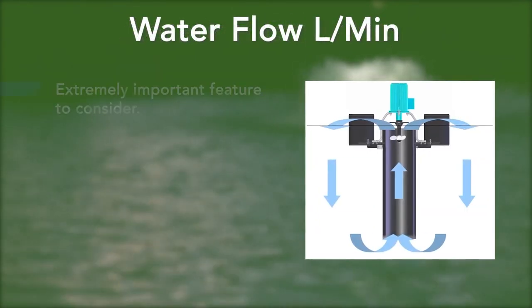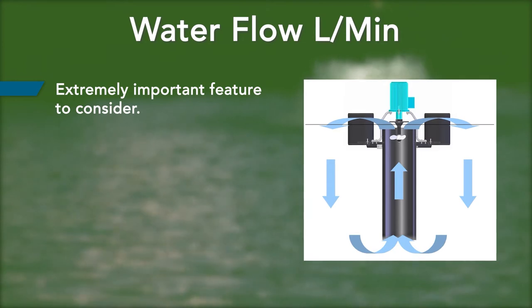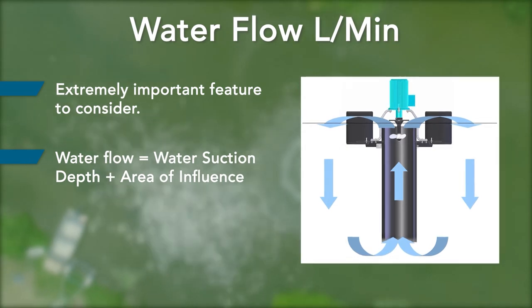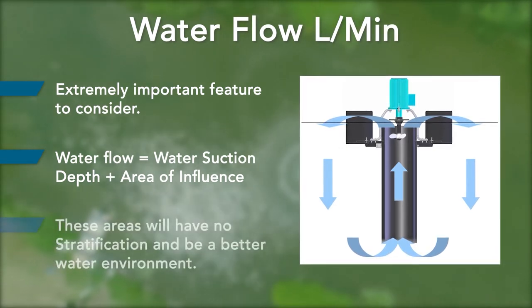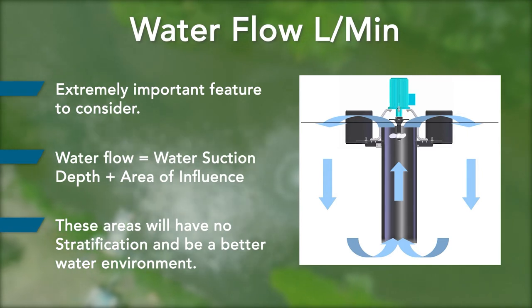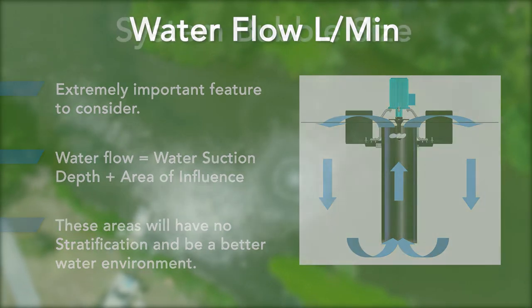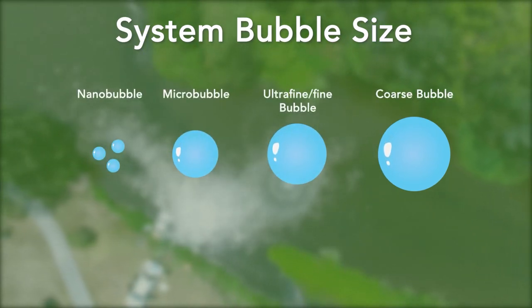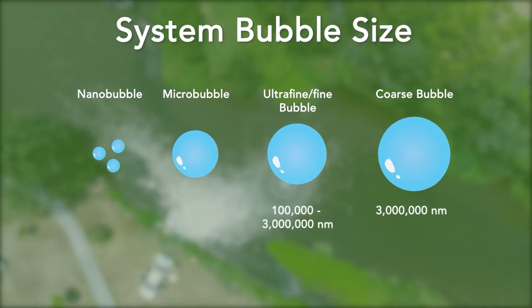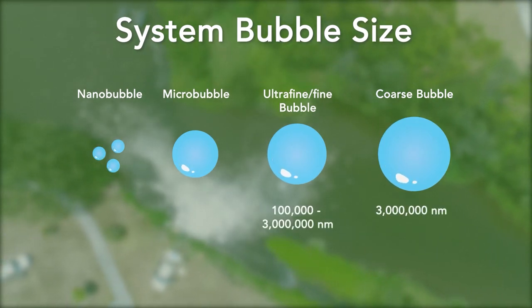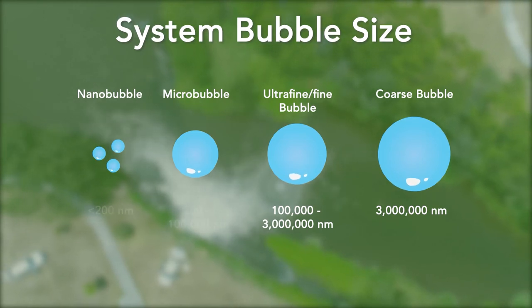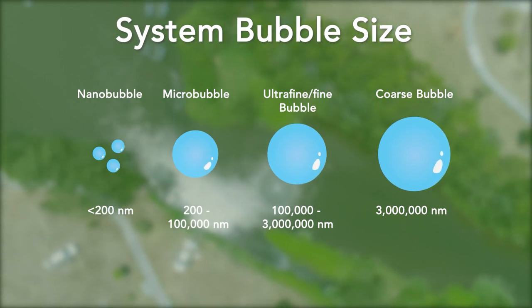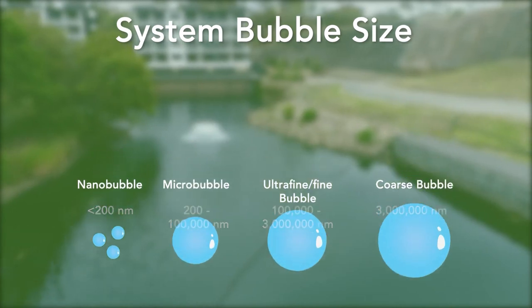Secondly, an important feature to consider is water flow. This must be considered when choosing an aerator. The water flow refers to the water suction depth and the area of influence of a surface aerator. In these areas the water will be oxygenated and mixed with no stratification and generally a better water environment. Thirdly, one of the most important factors when looking at an aeration system is bubble size. A large bubble will rise to the surface quickly and explode, releasing small amounts of oxygen to the water and gassing the majority back into the atmosphere. The smaller the bubble, the longer it is in contact with the water, therefore more oxygen is transferred as it takes longer to reach the surface.